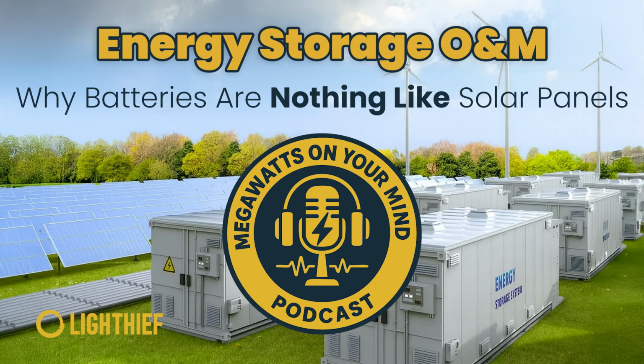Lithium-ion offers the best balance of parameters. High energy density, high round-trip efficiency of 85 to 95%, long cycle life of 3,000 to 8,000 cycles, fast response time in milliseconds. But lithium-ion is a category containing many different chemistries.